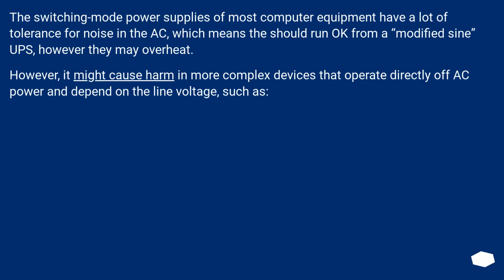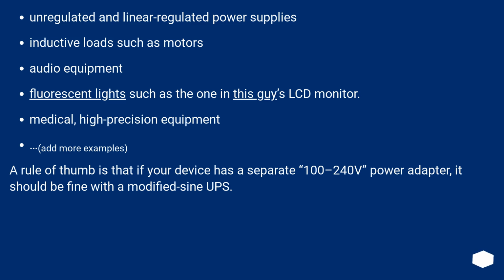The switching mode power supplies of most computer equipment have a lot of tolerance for noise in the AC, which means they should run okay from a modified sine UPS, however they may overheat. However, it might cause harm in more complex devices that operate directly off AC power and depend on the line voltage, such as unregulated and linear regulated power supplies, inductive loads such as motors, audio equipment, fluorescent lights such as the one in this guy's LCD monitor, medical, high-precision equipment. Add more examples.